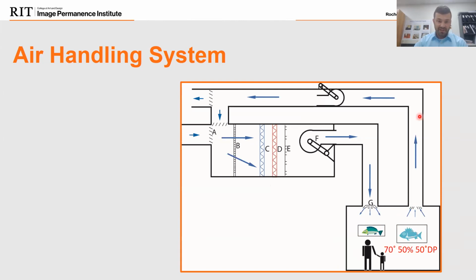So we're going to be pulling this air down through our return. We're going to exhaust a little bit of the air, return a little bit of that air, and bring in some outside air. At every step, I'm going to explain what's happening as we go through the filters, the cooling coil, and the heating coil, and what each one of those components is doing. In this scenario, everything's working perfectly, 100% perfect. Nothing's malfunctioning, and we hit the set points that we wanted. So we're aiming for 70 degrees and a 50-degree dew point, and we're going to pull that back.